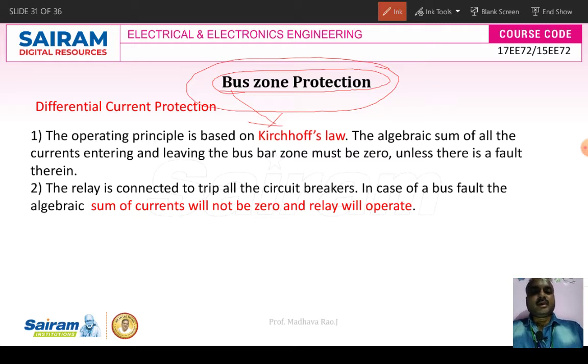Here, the bus zone we can consider as feeders, so different types of feeders. We'll see how the bus zone is connected to the feeders in the next slide and diagram. Here we are using differential current protection to protect the bus zone.